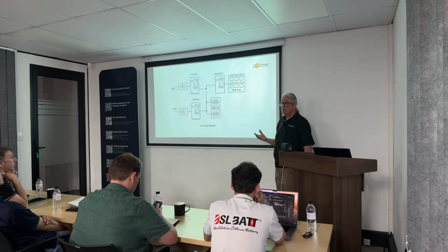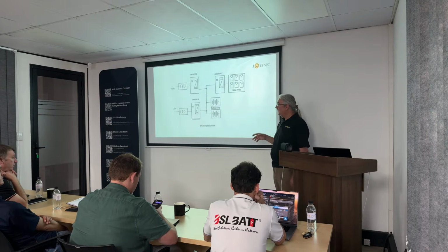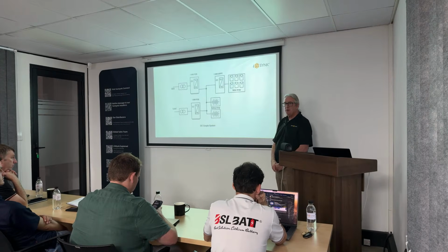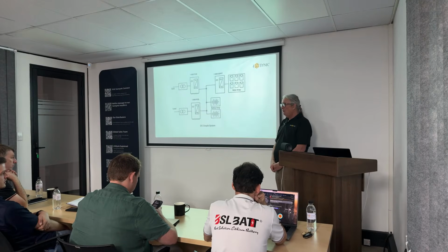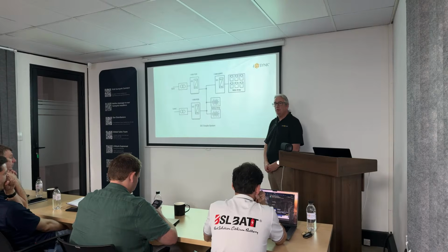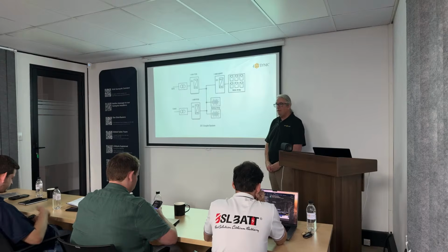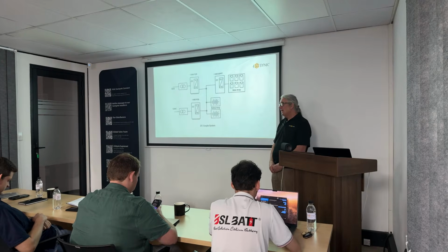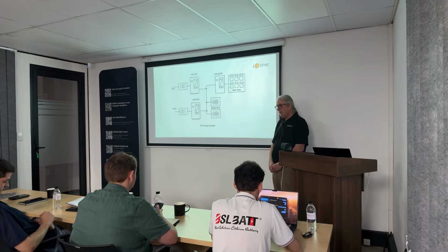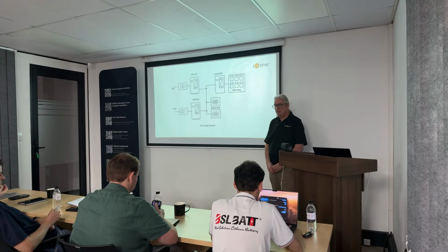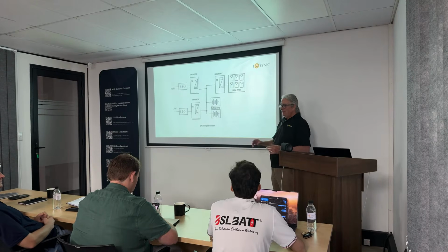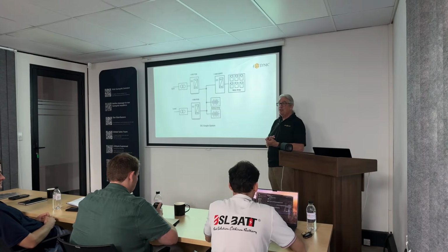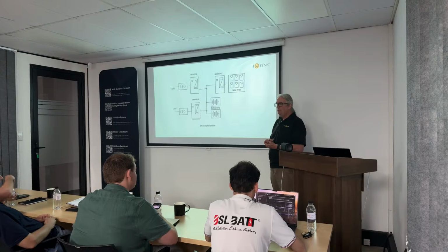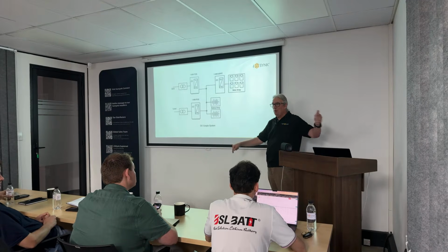The fact is, we really don't need a transformer, especially in South Africa, you don't need it, but some applications you do. People ask me about motors. Generally, if you're going to a variable speed drive, you've got a big motor, it's outputting on a variable speed drive, it will make no difference. The drive will handle it, it will control it, regulate the power going into it. If you're going onto a big old-fashioned motor, then you have got inrush currents, sometimes capacitors that are there because you've obviously got a massive reactive inductive load on the motor, and you've got power factor correction things, and suddenly the inrush, it'll see almost a short circuit. And so you have to be aware, and you have to look at the inrush current. The inverters will take a certain amount of overload. By adding a transformer, it won't fix that problem because you still have to put into the transformer what you get out of the transformer.